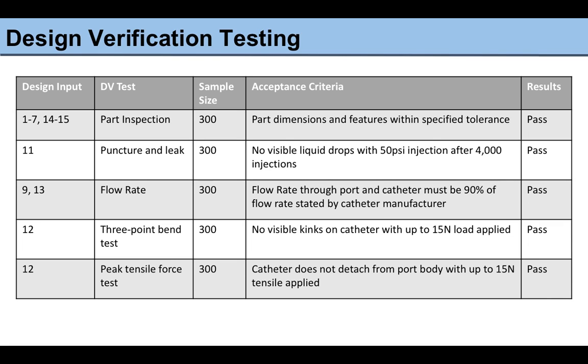We also had a flow rate test to make sure that our injections could travel through the port and through the catheter and be delivered to the patient with no obstructions. The acceptance criteria for this test was that the flow rate through the port and catheter must be at least 90% of the flow rate stated by the catheter manufacturer. And this is to make sure that the port and the connection to the catheter isn't restricting the flow through the catheter at all. And this test passed.